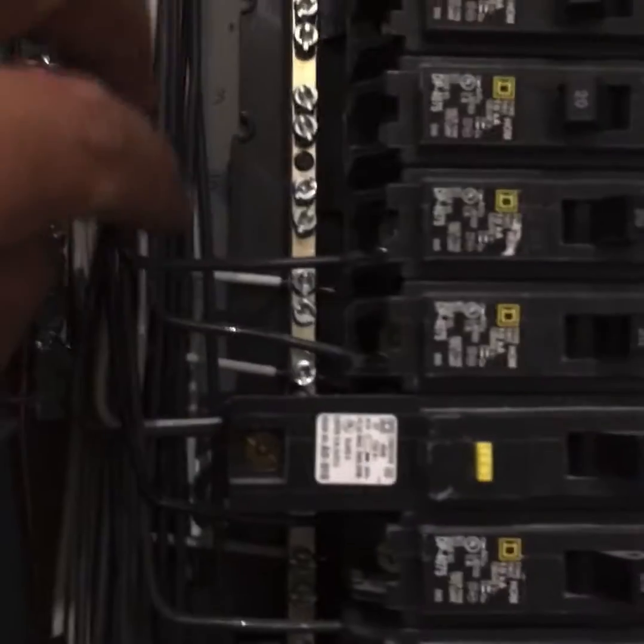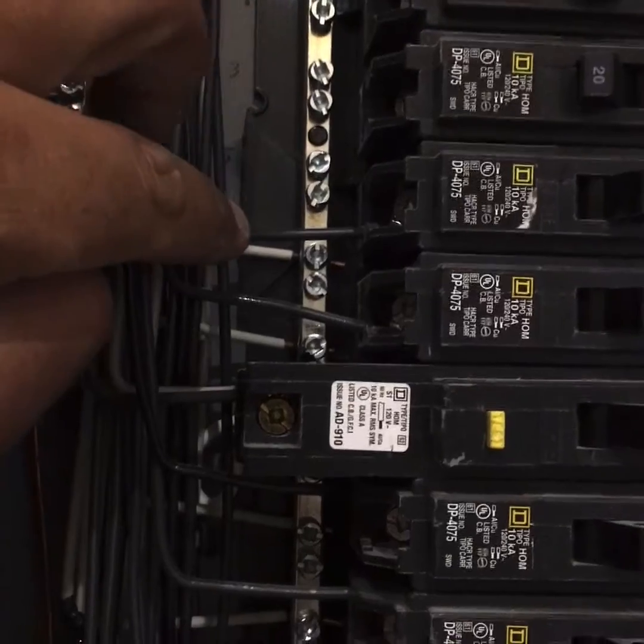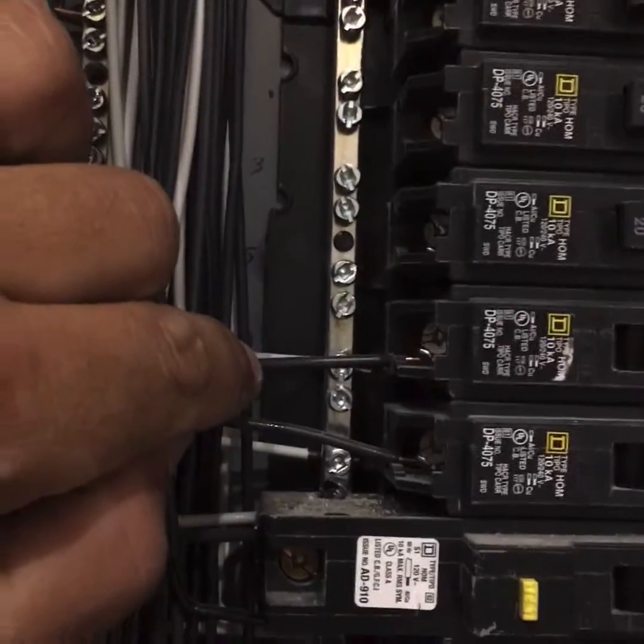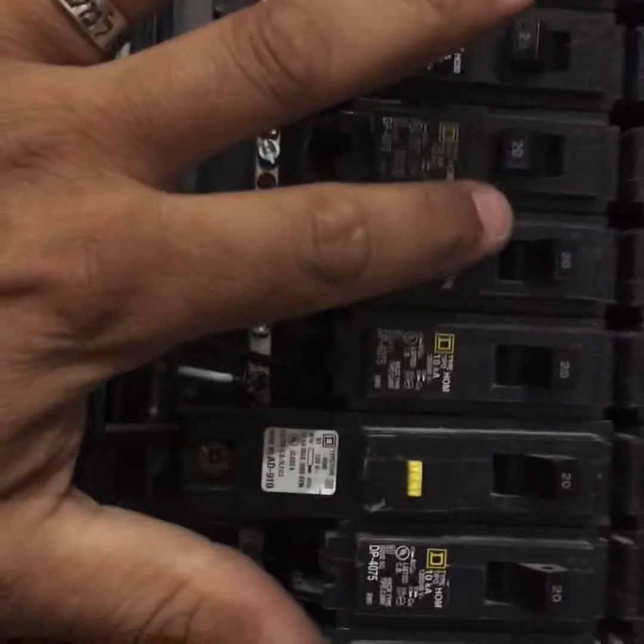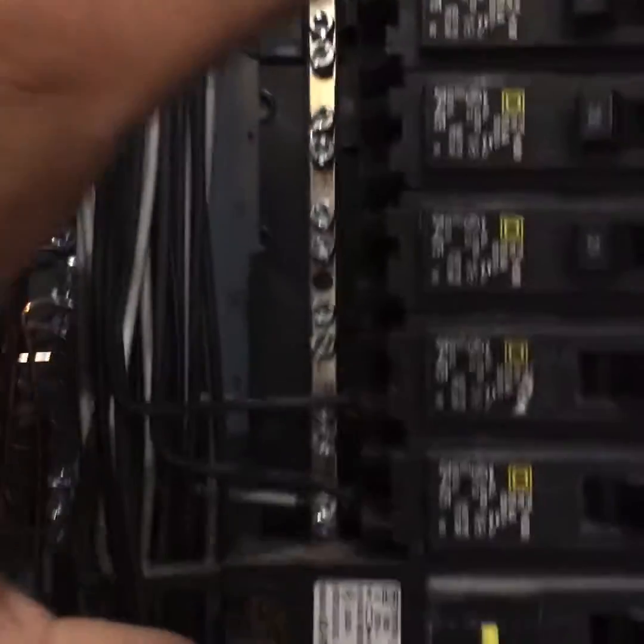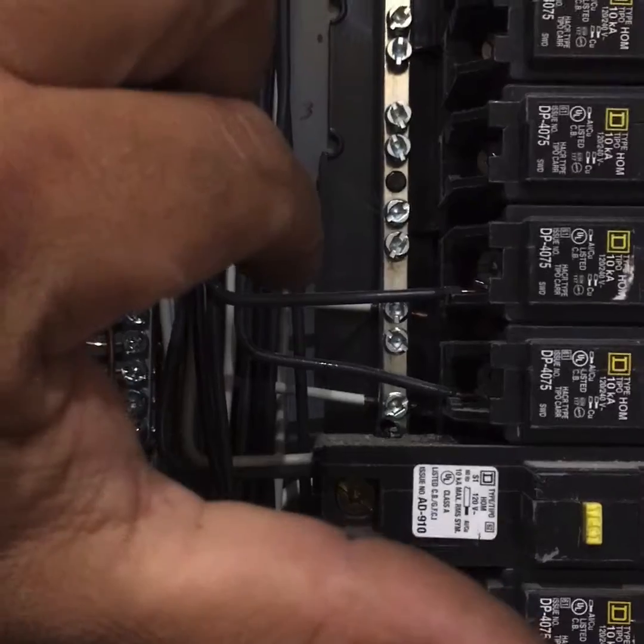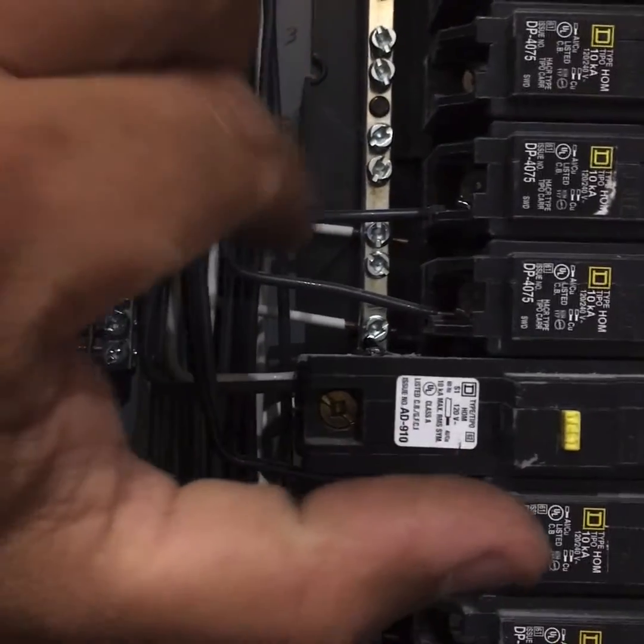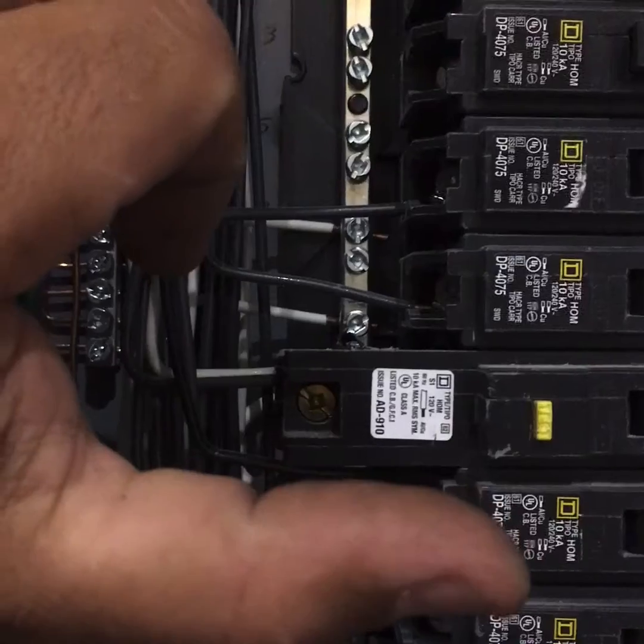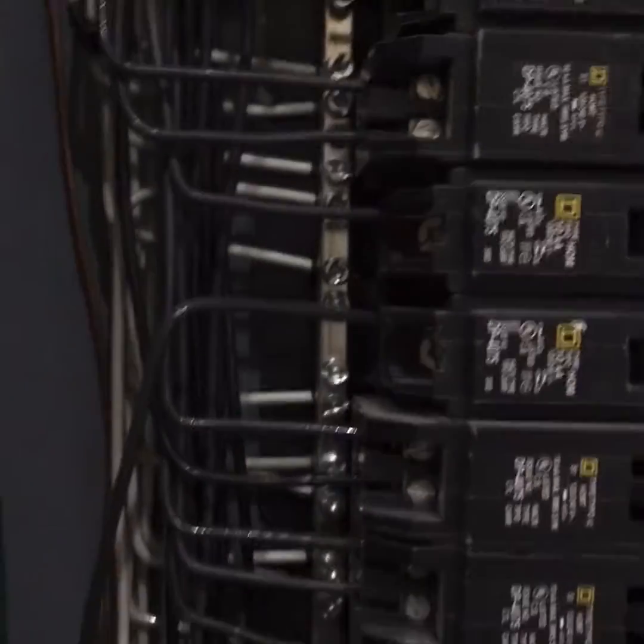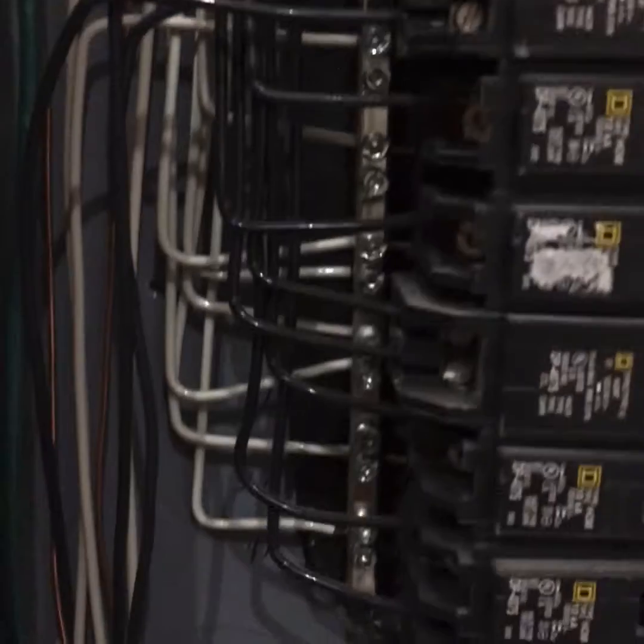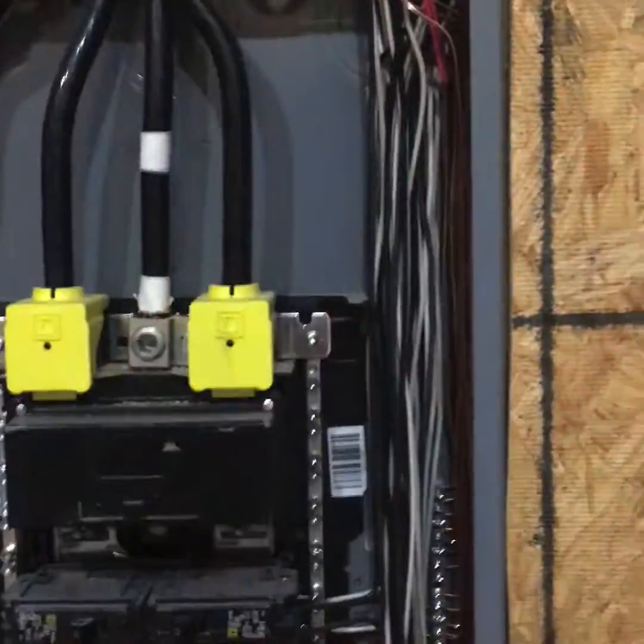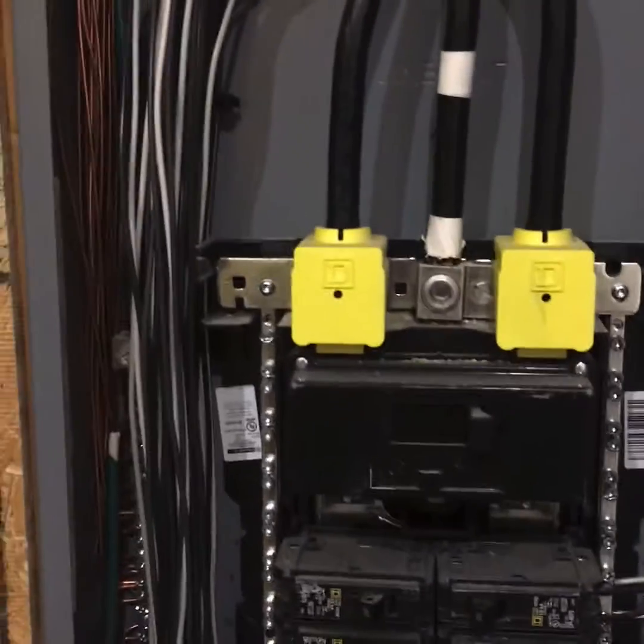Whenever I'm landing my power wire here, let's say line 1, directly behind it, you can see that is a neutral. That is the neutral that goes to this circuit. So that's circuit number 7? Well, that's the neutral for this number 7 circuit. So when I'm troubleshooting, I can isolate the power and the neutral really, really easily on every single one of those. It doesn't take a whole lot more extra time. From a troubleshooting standpoint, it can be very beneficial. So that's it. I always put an extra ground bar in. Not sure if I said that already. So I have one on either side. Makes pulling the grounds in a whole lot easier. But that's it.